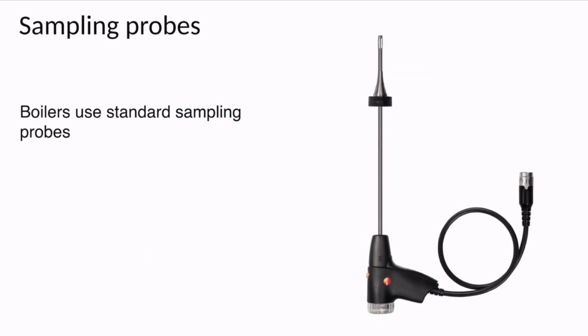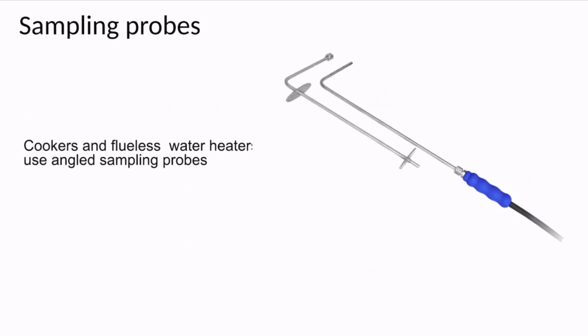Now the sampling probes you use, boilers use what they call the standard sampling probe. It looks like this. It's got that cone on the end, and that is your boiler sampling probe. Cookers, flueless water heaters, and flueless fires use angled sampling probes. These probes have got little holes in the end of them, or along the top of them. Make sure the holes are pointing downwards into the flow. So the products of combustion will generally be coming up out through what is basically a very short flue. Make sure the holes are pointing into the flow of the products of combustion.